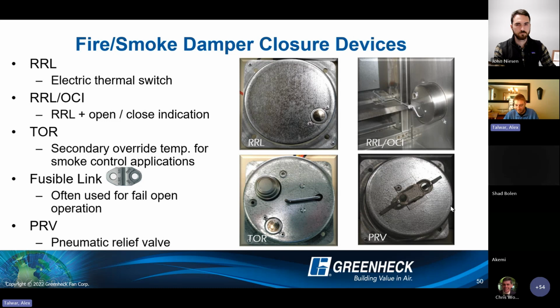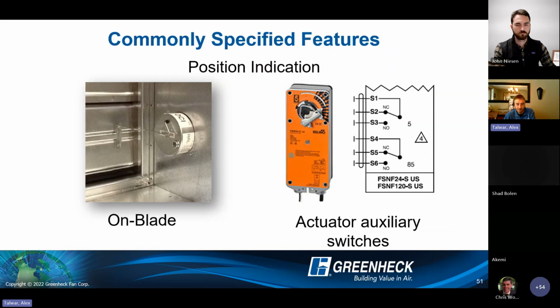And if you do happen to come across pneumatic actuators, the pneumatic relief valve is the activation device there. It's essentially a fusible link. Position indication, certainly common to want to know if your damper is open or closed and monitor that position. So the two options really are the OCI, the on blade indicator there, open closed indicator, or the actuator auxiliary switches, which will tell you when your actuator reaches the beginning or the end of its cycle.